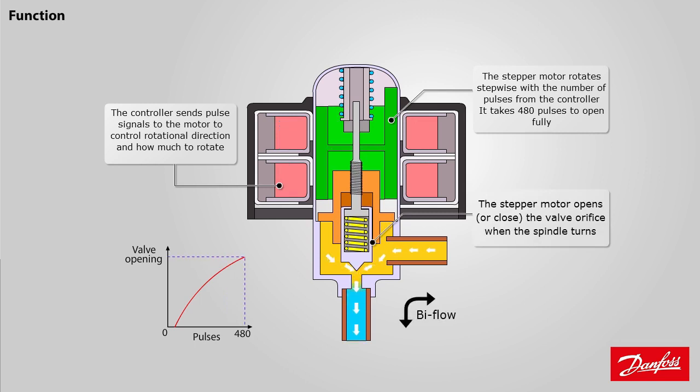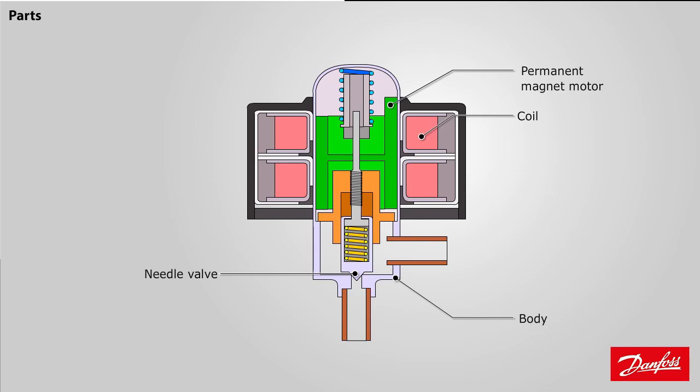When superheat is low, the EEV may respond by closing to allow less refrigerant to flow into the evaporator to maintain the desired cooling capacity and prevent excessive liquid refrigerant from entering the compressor.